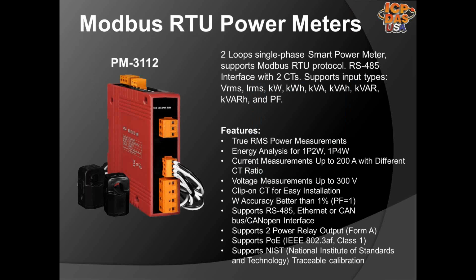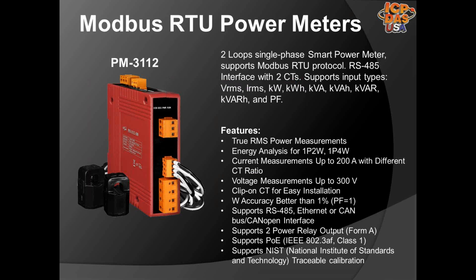PM3112 is a power meter that supports 2 loops single-phase measurements. It communicates over 2 copper wires for RS-485 communication. It also has 2 power relay Form A outputs, so you can turn devices like lights or sirens on or off with it based on the energy measurement data.